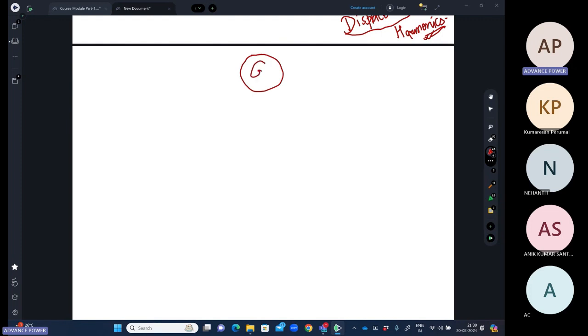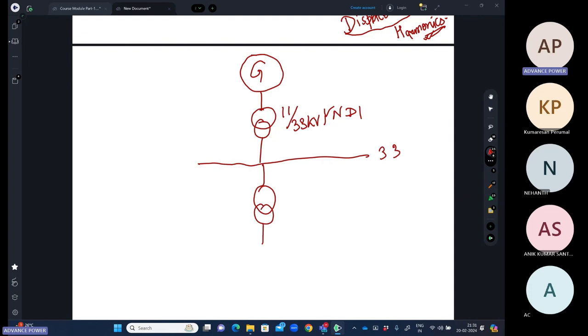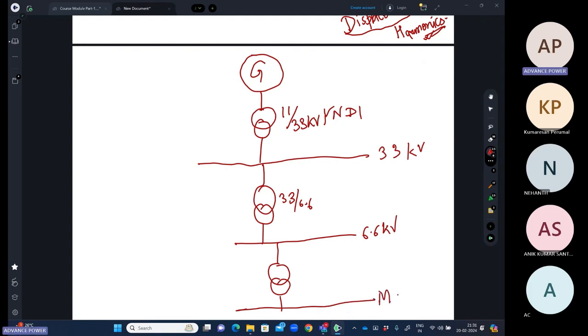Suppose a generator is here. It is generating 11 kV. We have a generating transformer which is 11 by 33 kV. All those parameters I will discuss in detail when we discuss vector group, percentage impedance, and those concepts. Then we'll have a 33 kV board. Then suppose 33 by 6.6 kV. Then further we'll have a PMCC, so this is 6.6. We have the MCC, which is 415 volts, so 6.6 by 0.433 kV.